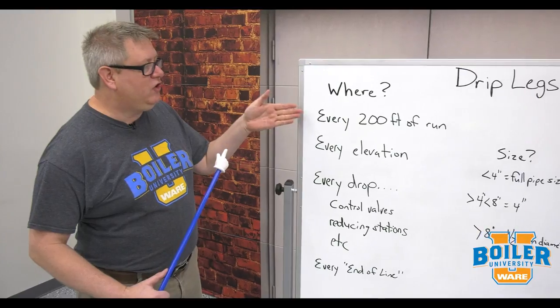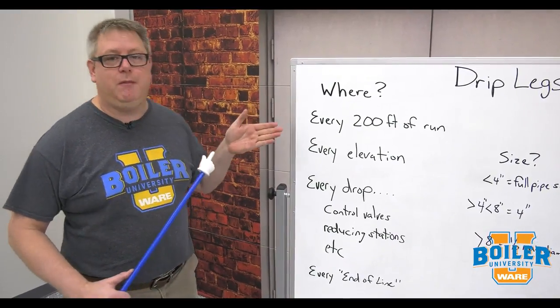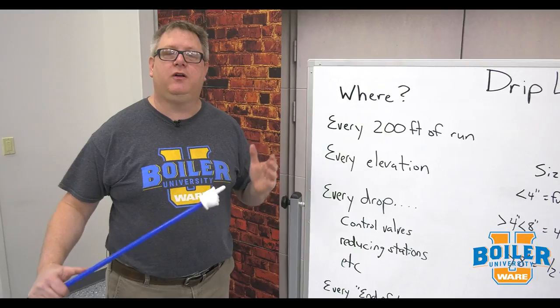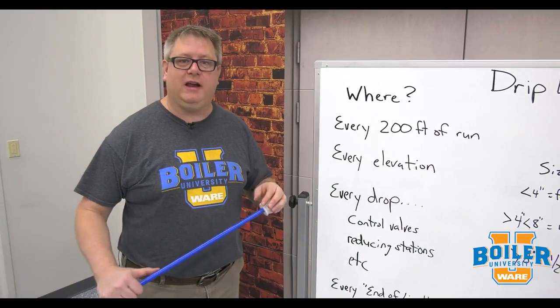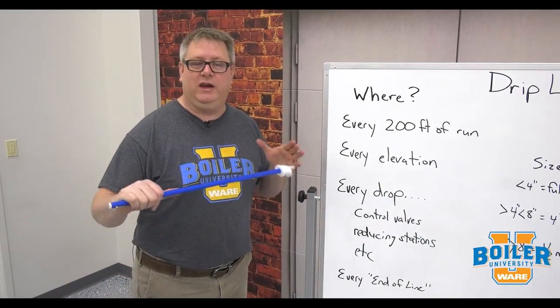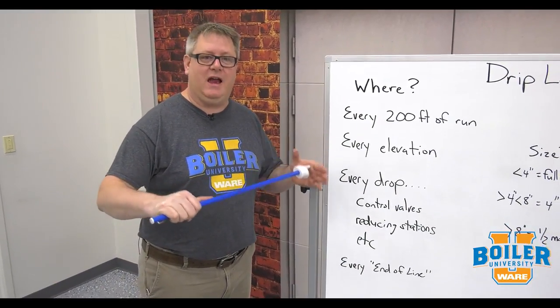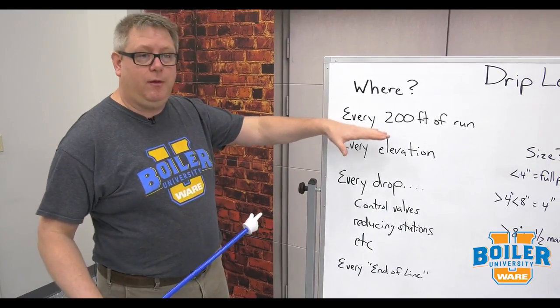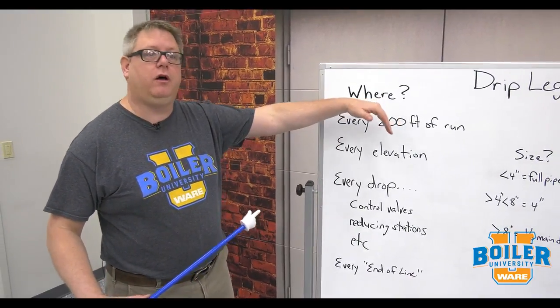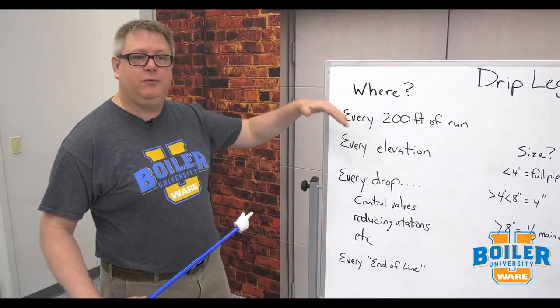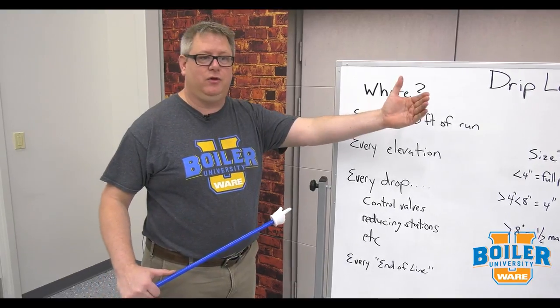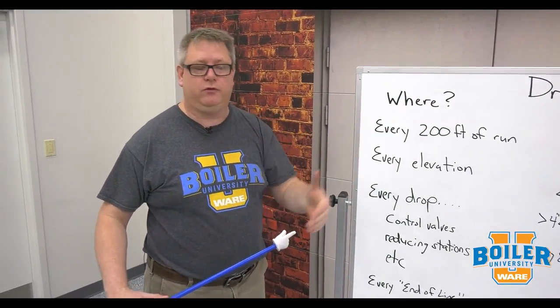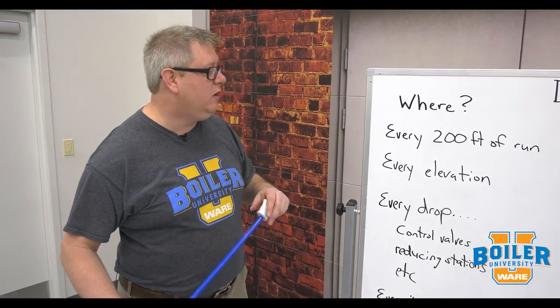First, every 200 feet of steam main run we want a drip leg, because we're generating condensate in that run and we need to get rid of it at intervals. This is a rule of thumb — you can get away with a little bit longer sometimes, but if you cross outside through a breezeway you may need to make it shorter because there's more condensate being generated.